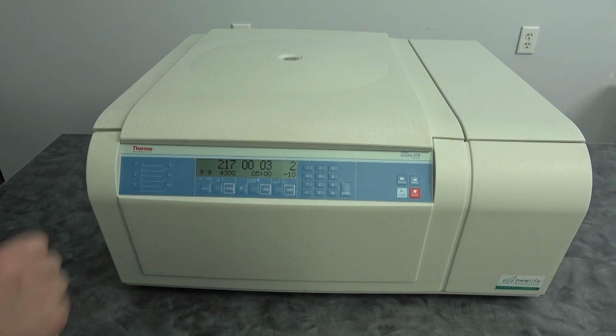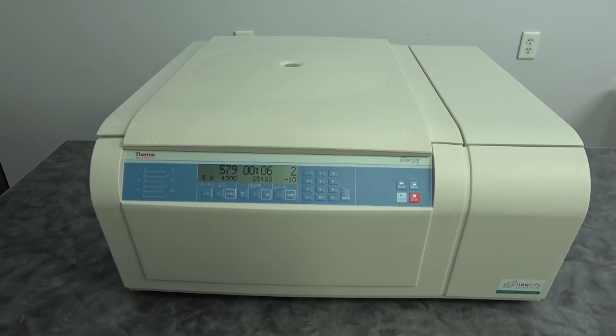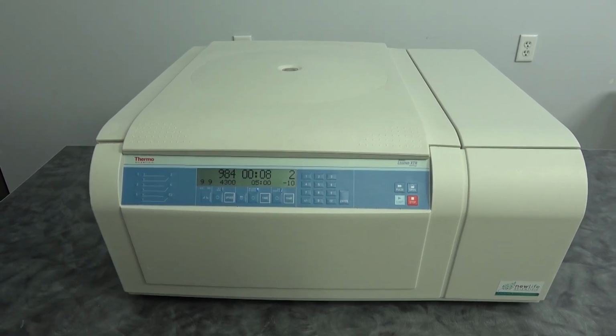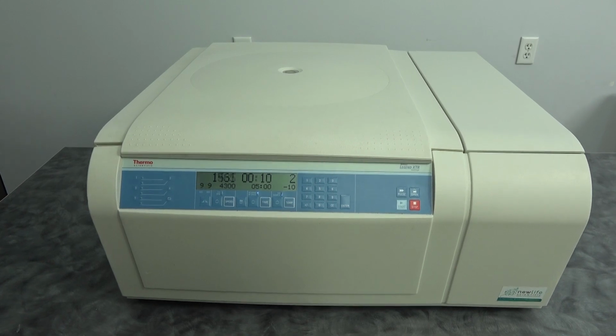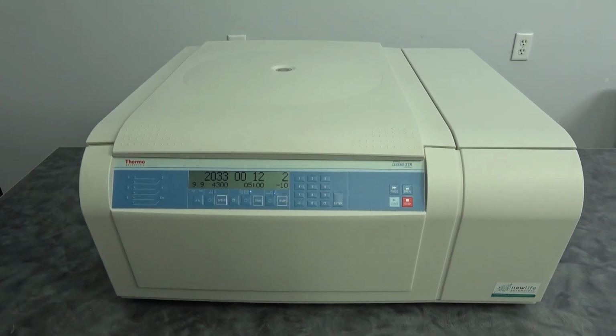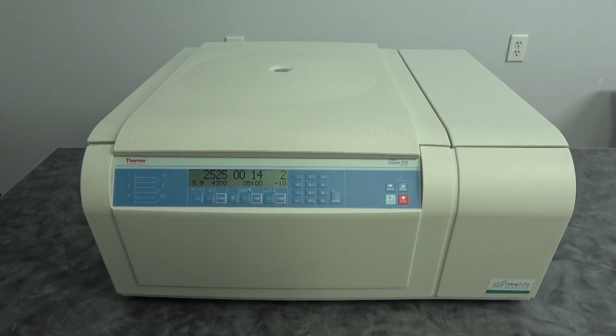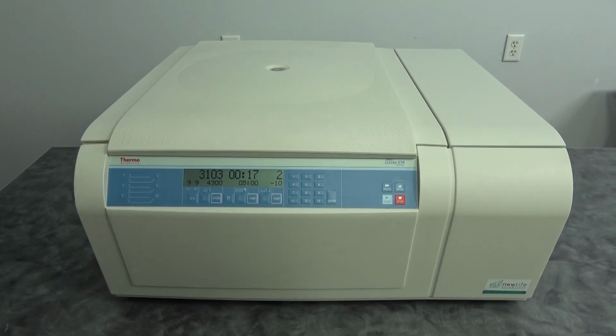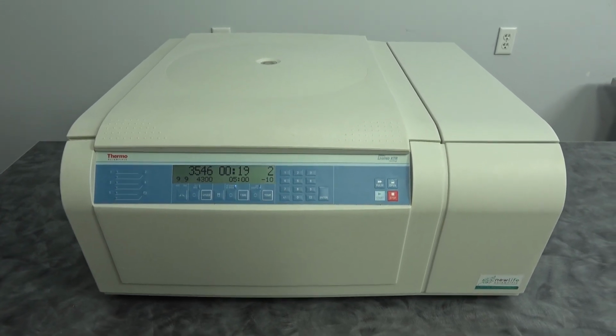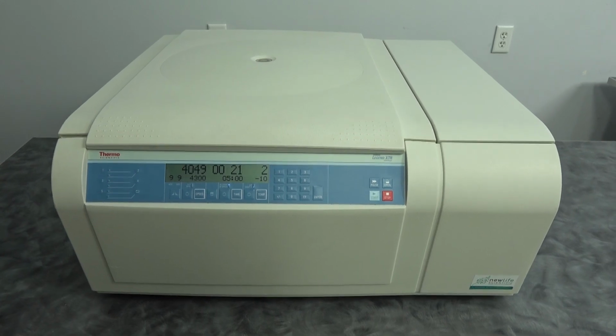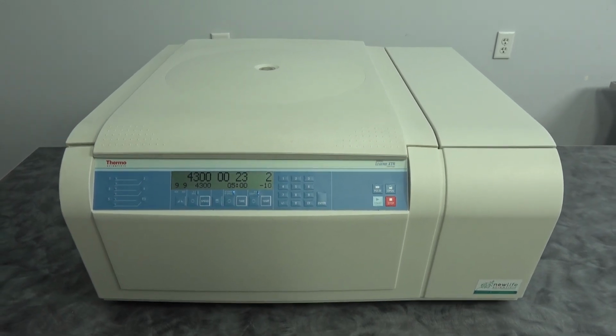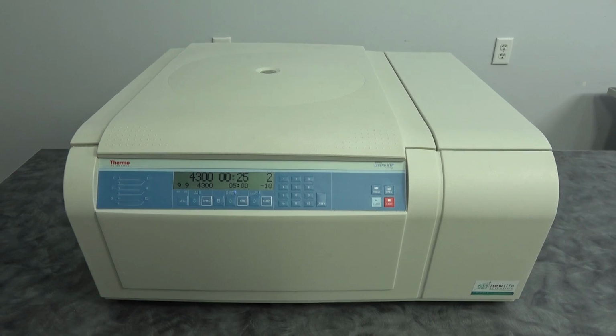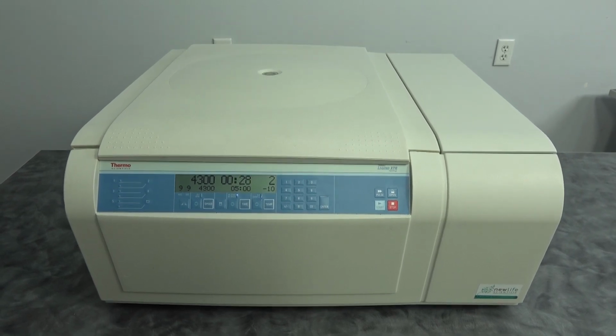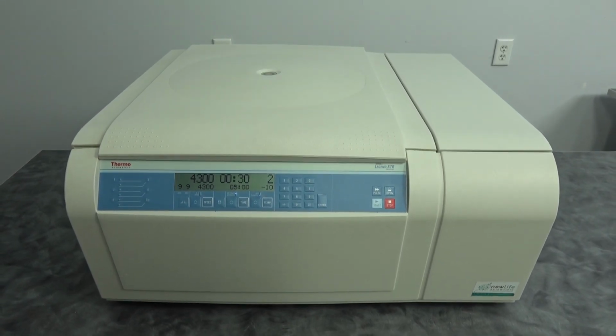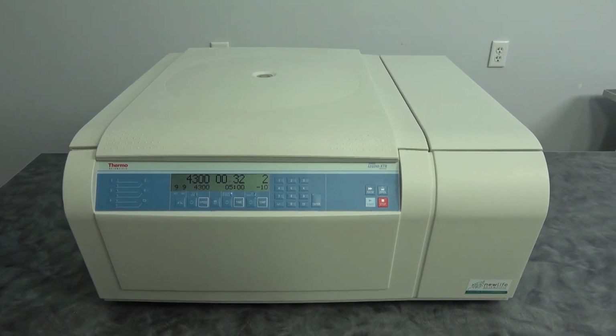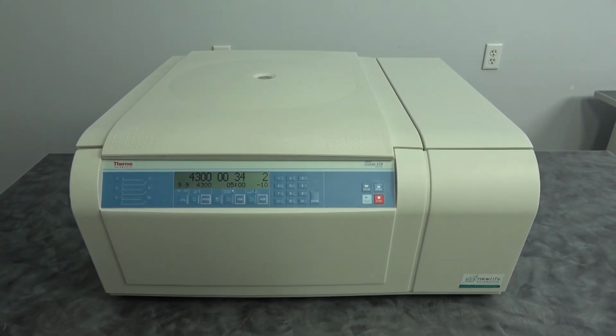Now while that's spinning up, I'm going to talk a little more about what happens if you don't have your manual for either the rotor or the centrifuge. Please reach out to us. We're happy to provide those manuals to ensure that you're using your equipment properly and safely. In addition to knowing what you can spin your rotor and centrifuge at, you want to take a look at your samples and what tests you're trying to run to ensure that you're making runs in accordance with your samples as well. So as you can see there, the unit's up to speed. That's all there is to using this centrifuge and getting it up and running.